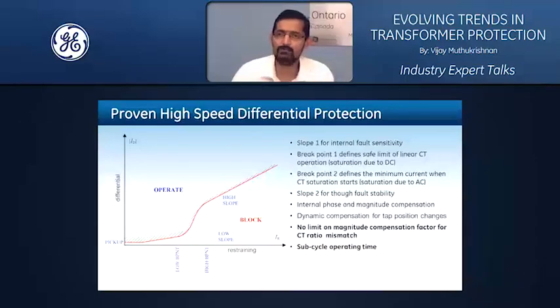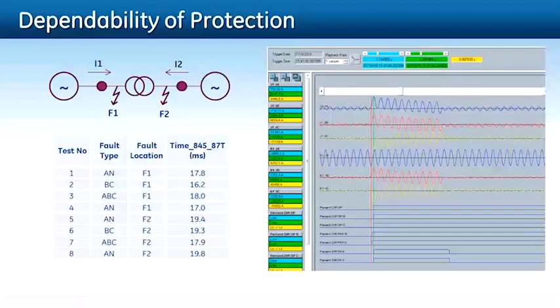Now, what are the proof points around it? A transformer protection relay has to go through a significant amount of real-time digital simulation type of dynamic testing, like the one you're seeing here, results out of our 845 transformer protection relay. Here is a sample. You have a transformer system with sources feeding on either side, and you can simulate different types of faults, phase-to-ground, phase-to-phase, and three-phase faults in the zone of the transformer to simulate an internal fault. That's what you see on the table to my left. This is a sample of the test cases we have run, but there can be hundreds of cases simulated using RTDS to study the performance of the transformer protection relay. This is how you prove the speed of operation of a transformer protection relay.